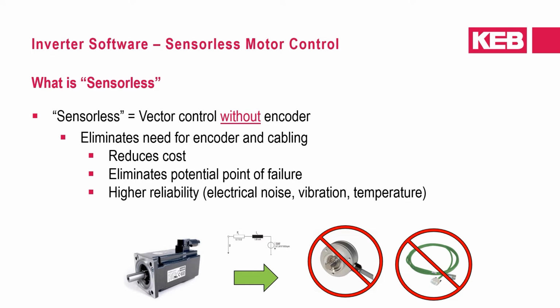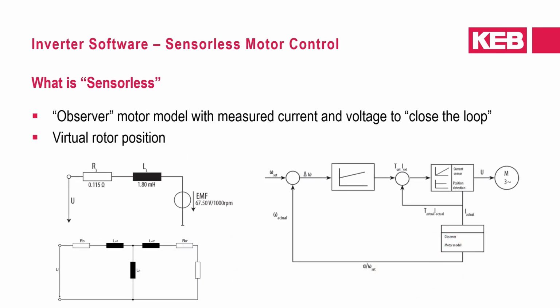This eliminates the need for a motor encoder and cabling, which reduces costs as well as eliminates a potential point of failure and increases system reliability against factors to which an encoder may be susceptible, such as electrical noise, vibration, or temperature. Instead of encoder feedback, sensorless control utilizes an observer motor model based on motor characteristics and utilizes the actual measured motor current and voltage to close the loop, and also creates a virtual rotor position.